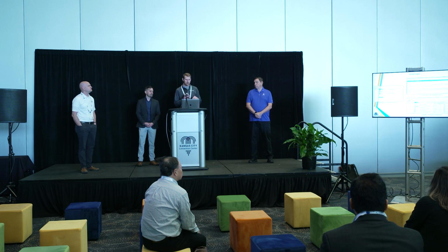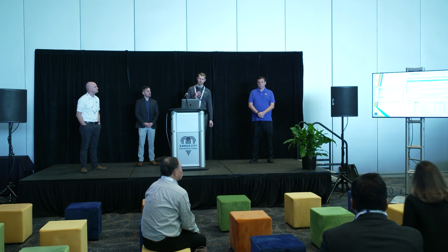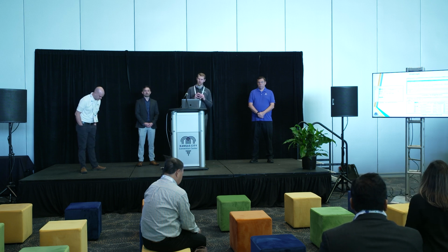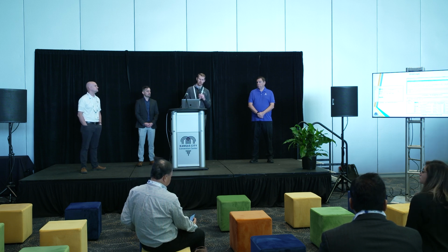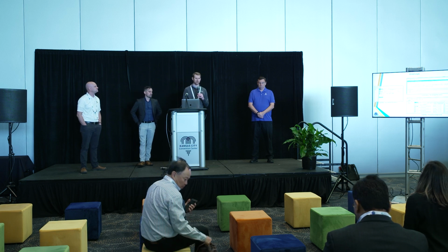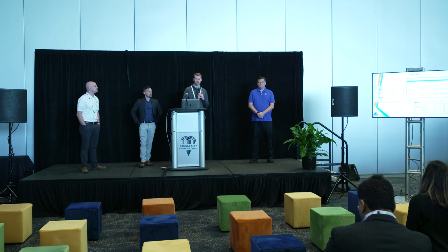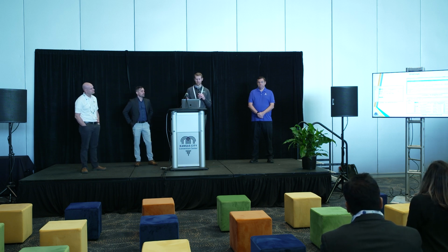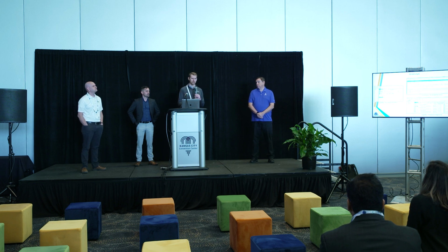There's 3 different logic elements that we included on this to be able to capture the success rate and put together these counters. In the Orion platform, there are different packages you can add, and one of them is Logic Pack. The reason we have Logic Pack is for basic arithmetic and applications. It's basically to say that simple math doesn't need to be hard. In this case, we were able to set up primary and secondary inputs for the substation side so that we could capture either the CBRS or the Anterix network and funnel those into a single bucket. So if one of those networks happens to go down, we have failover on that communication and are still able to get the data input.